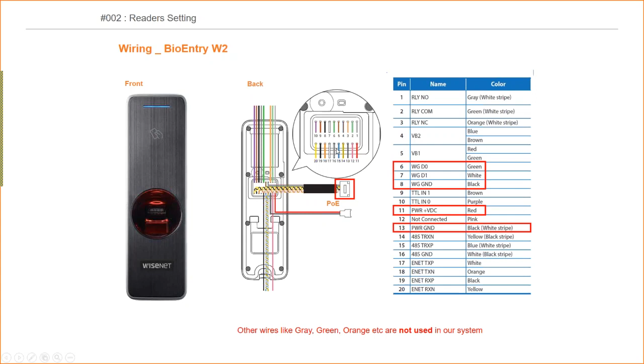Another misunderstanding is that if you're using a fingerprint reader, TCP/IP alone is not enough. You should also connect the fingerprint reader to the board. For example, the fingerprint PoE is for power and data, but you should also connect the other ports, data 0, data 1, ground, to the controller. So just remember, whenever you use a fingerprint reader, you need a Cat6, and you need another Cat6 for these four cores, data 0, data 1, ground. You have to use a separate cable for sending the access control data, in, out, and wiegand output. So two cables are required.